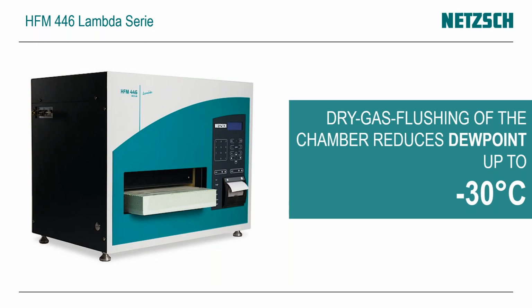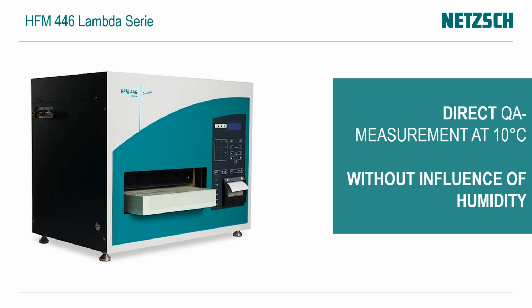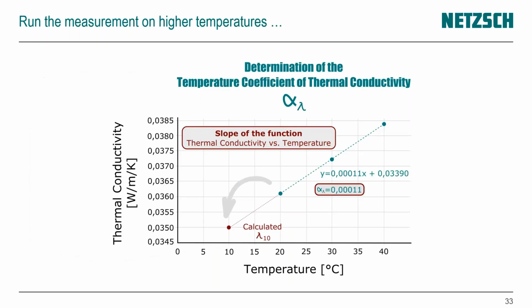That means if you flush it before you enter your sample, you close the door and you start your measurement. The risk of condensation inside of the instrument, inside your sample and on the plates is reduced to the maximum. So that means in that case, you have a chance for a direct QA measurement at 10 degrees C without influence of humidity. Or what you also can do, run a measurement on higher temperatures.